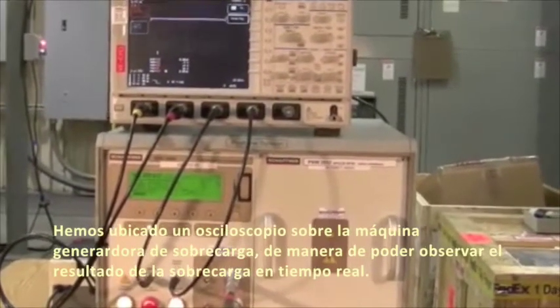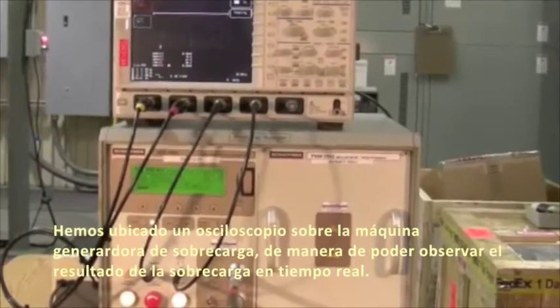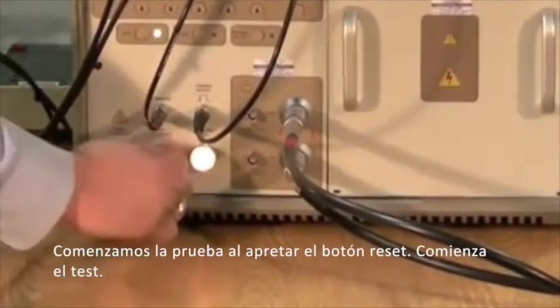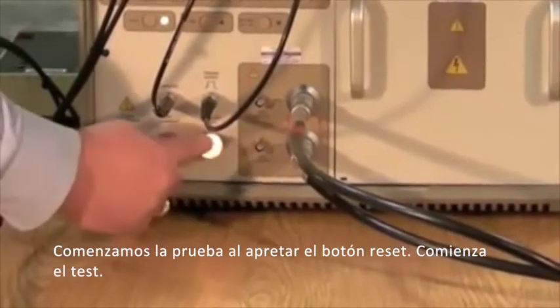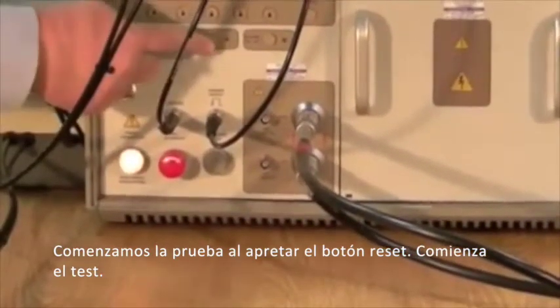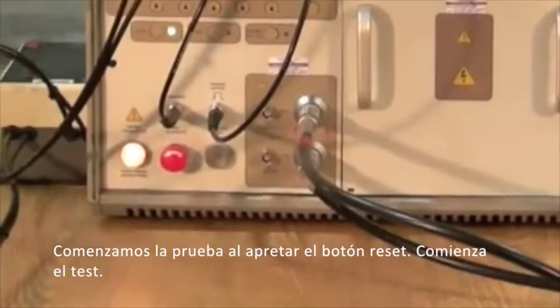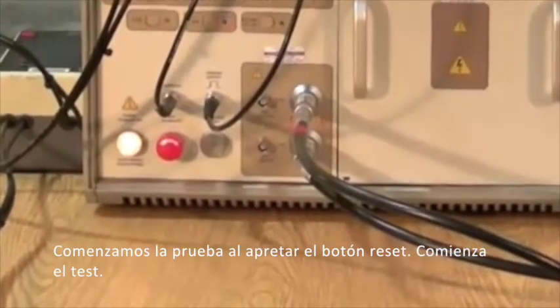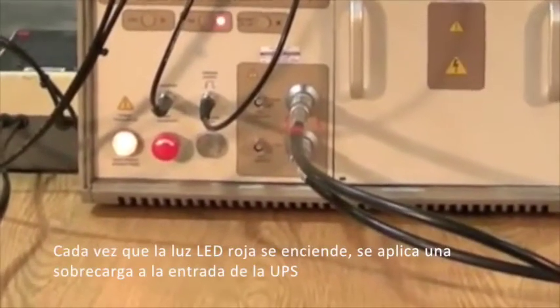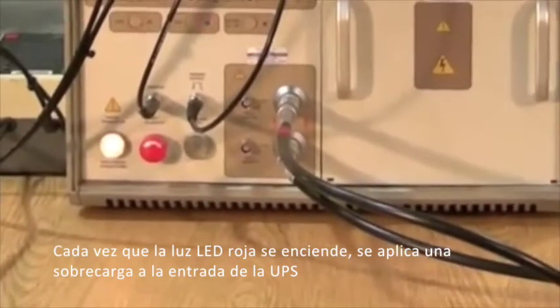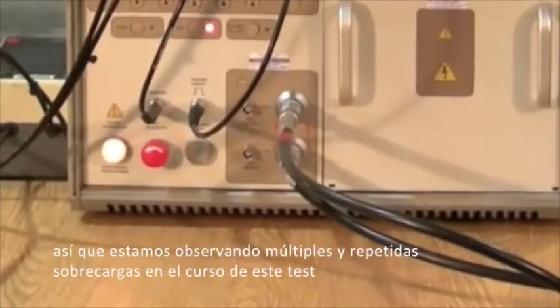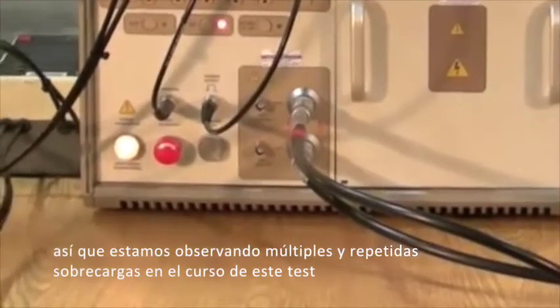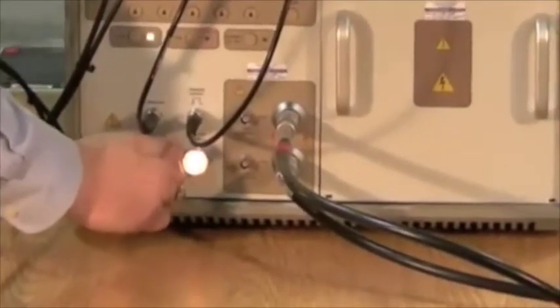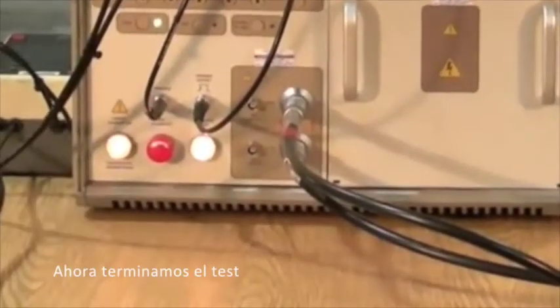We've placed an oscilloscope on top of the Keytek machine so we can see the surge and the resultant output in real time. Now we begin the test by pressing the reset button and press run. The test begins. Each time the red LED lights, a surge is being applied to the input of the UPS, so we are seeing multiple repeated surges during the course of this test. Now we end the test.